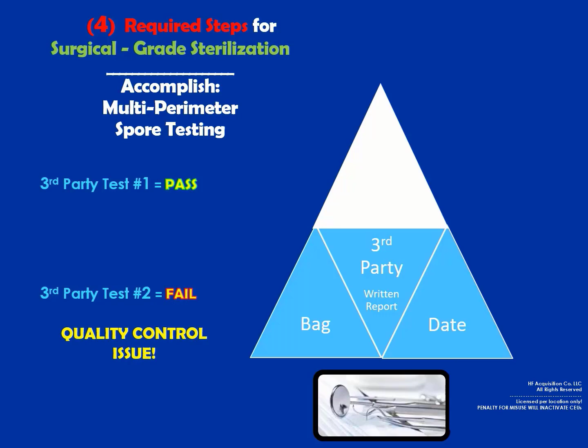To remedy this, you must now monitor and track this using a multi-parameter indicator spore strip in every processed load. It will confirm that time, temperature, and pressure are met. Traditional heat-sensitive tape or bags only measure that temperature was met. Using a thermal printer or multi-indicator bags are also acceptable. This step establishes a tighter margin for error when monitoring sterilization, and you will be able to monitor the quality control of your instruments from batch to batch, not week to week. This step elevates your quality control when processing instruments to the surgical grade.